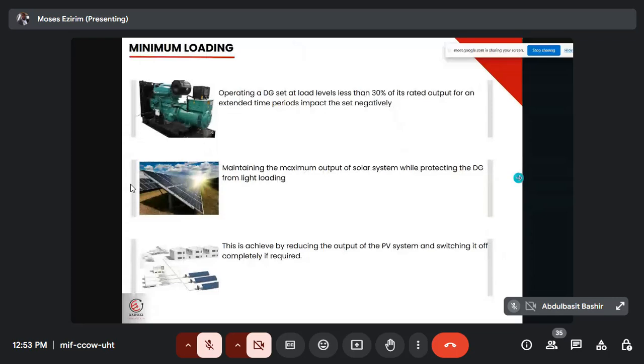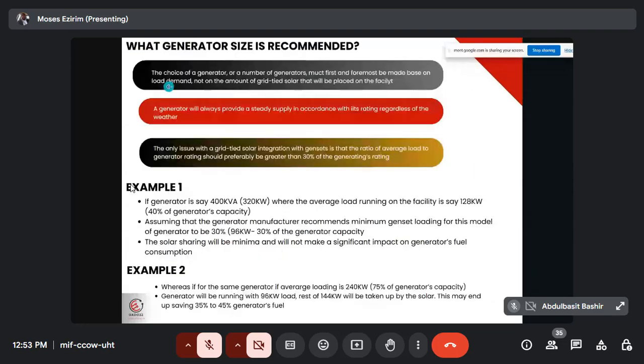What generator size is recommended? The size of a generator, or the number of generators, must first and foremost be based on demand, not on the amount of grid facility. What this is trying to say is that you must size the generator based on the load demand.